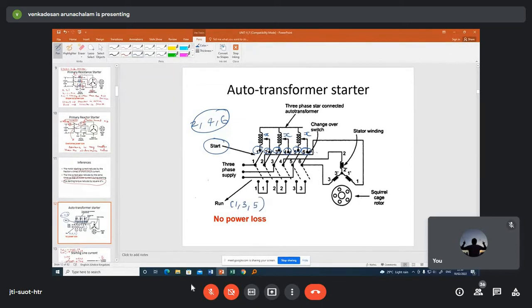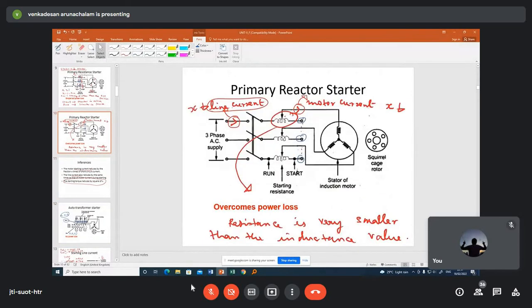Right? It is a very simple concept. During starting condition, the maximum value of reactance is added to the stator winding. During running condition, no reactance is added to the motor winding because the switch is there to regulate the current. So this connection can be done using a mechanical switch or any other switch, right? So that is nothing but your auto transformer starter. Here the stator winding is connected in star form and the auto transformer starter is connected in star form.